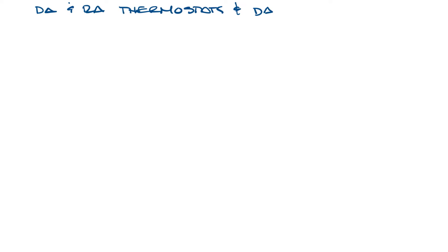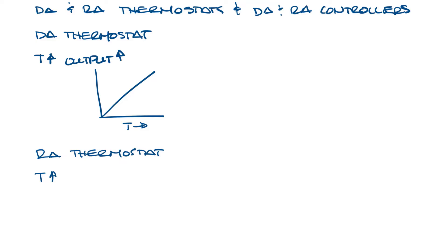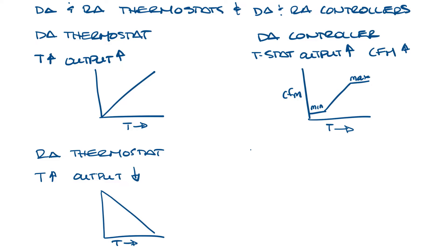You can have direct acting and reverse acting thermostats and direct acting and reverse acting controllers, and any combination of those on your VAV box. In a direct acting thermostat, when the room temperature increases, the thermostat output increases. In a direct acting controller, an increase in thermostat signal would cause the controller to increase CFM, with a min and a max and a modulation range in the middle.